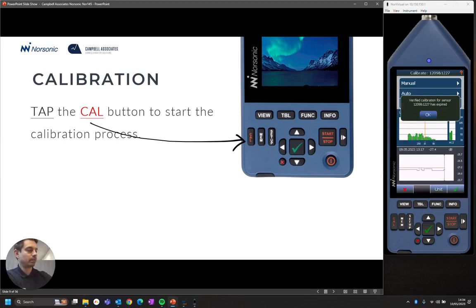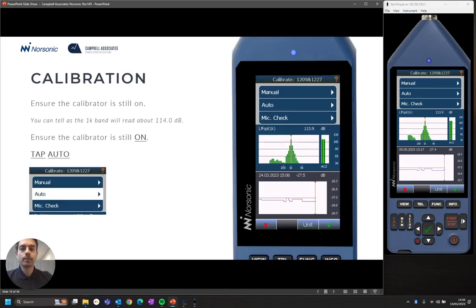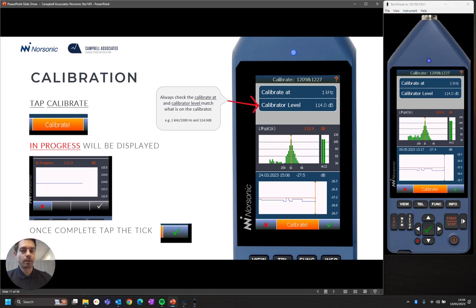So I'm just going to place the calibrator on the end of my microphone. Now you cannot see what I'm doing. I've now placed this on the end of the microphone, and you will see the level increase. I did have a little warning there, so the meter will remind you when it's due for calibration in the 2 years' time. So the next step is to tap on the auto in the middle, and then once you've done that, you need to press the calibrate button, which is at the bottom.